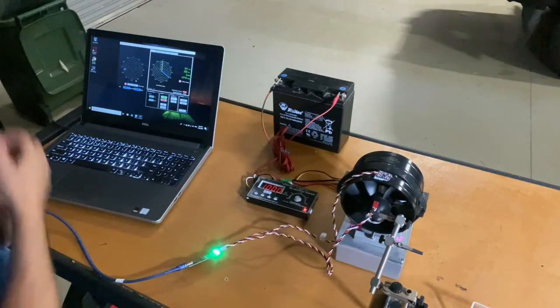Alrighty, so we've measured our vibration level, and the software has gone back and analysed the data, and it has identified that we need to apply a 0.1 gram weight, or correction weight, to the EDF impeller, or to the hub I should say, in a direction which is say 100 degrees counterclockwise to the location of the white marker.